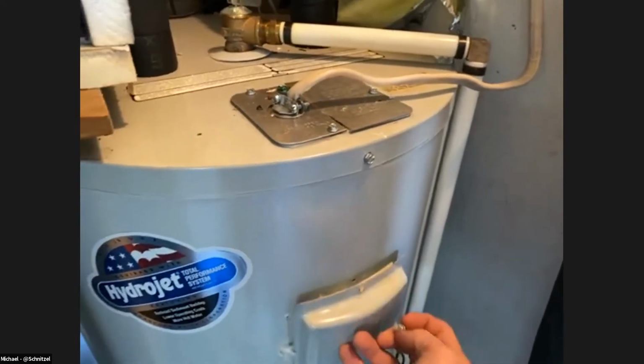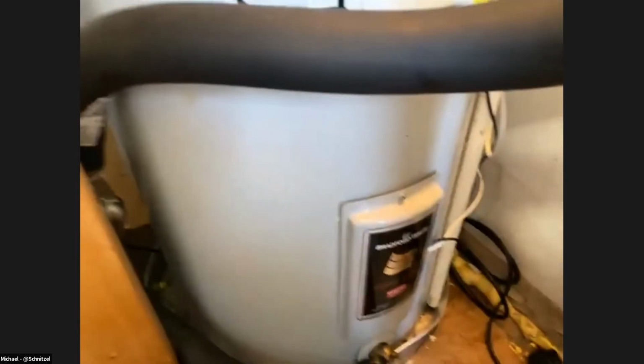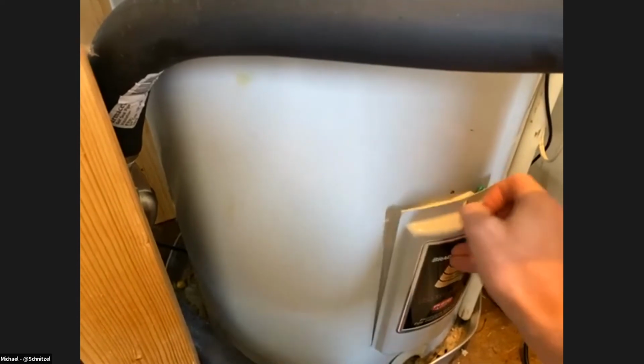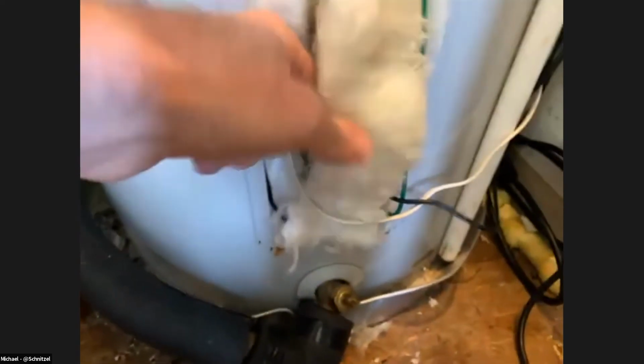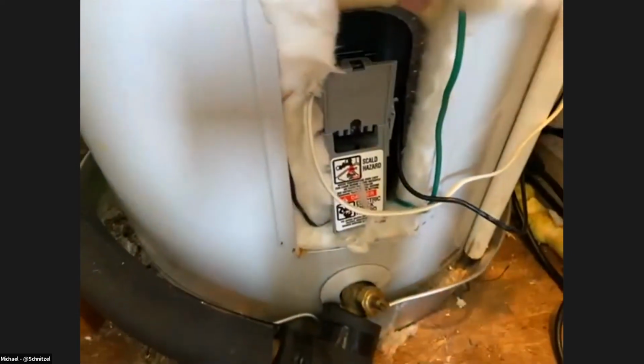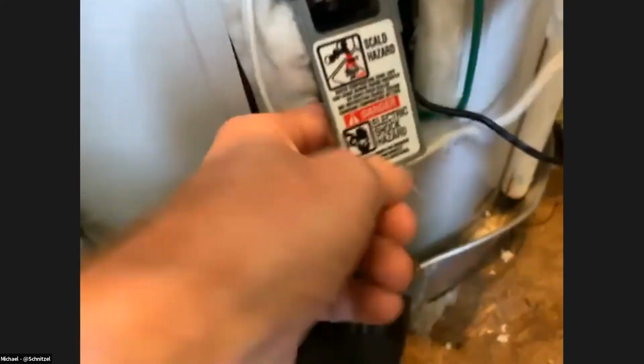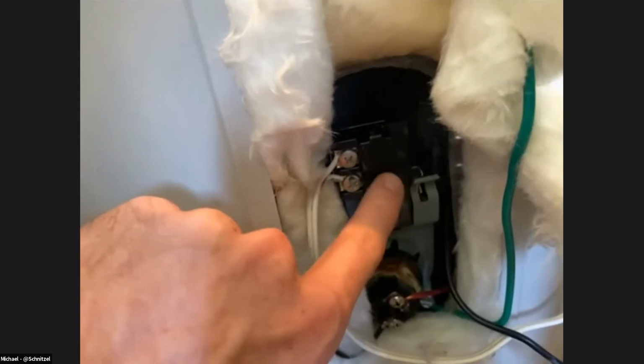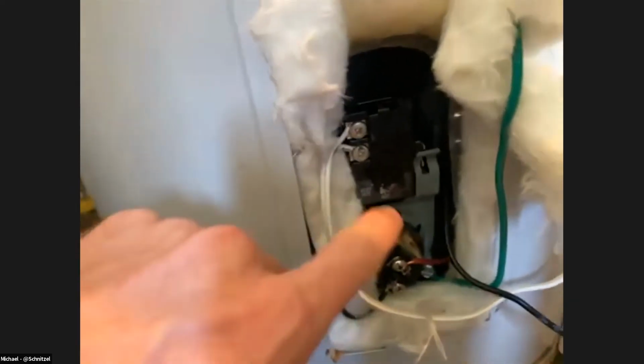Let's actually look at how this is converted. If we open this access panel, we get to the two thermostats, there's one here and another one as well. Let's look at the lower one since it's easier to see. You can see the insulation, the whole tank is very highly insulated, about 3-4 centimeters. Back here are the thermostats. If I remove this, this is the thermostat, it touches the back wall of the water heater, which is super hot, too hot to touch. Inside is the bimetal piece I explained before, where the metal either makes contact or not depending on whether it's hot enough. There's also a setting here you can switch to change the temperature.